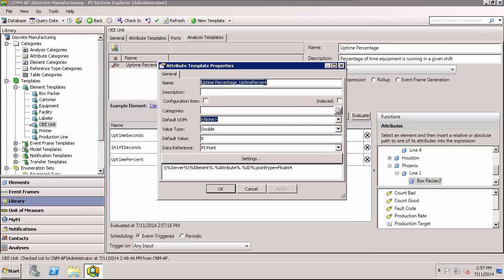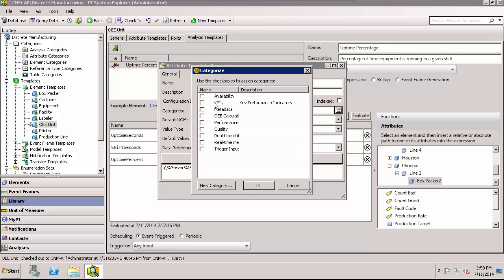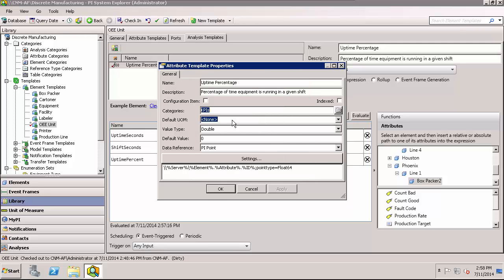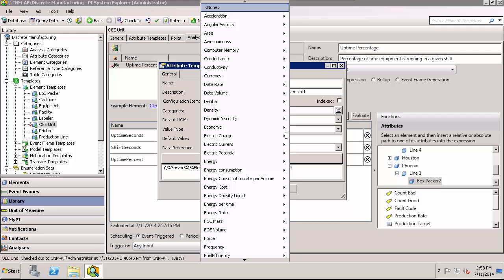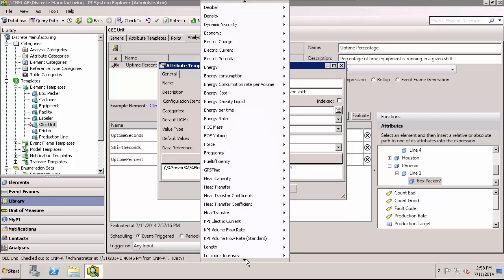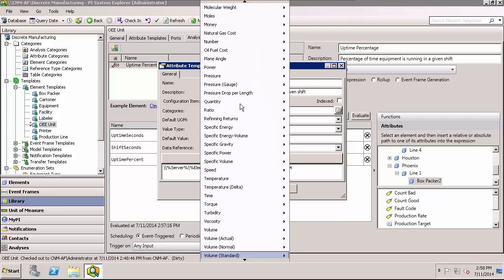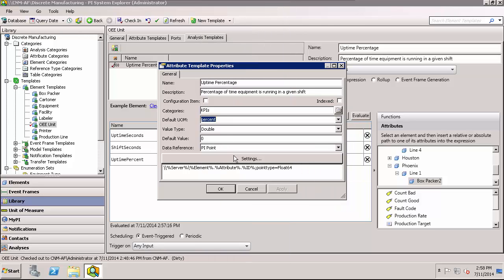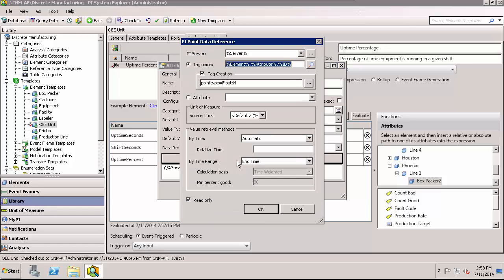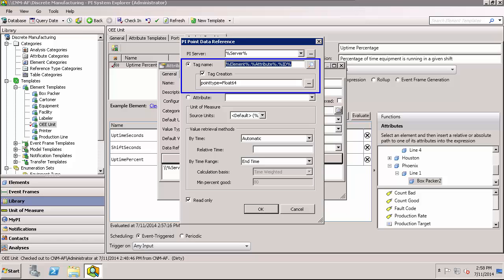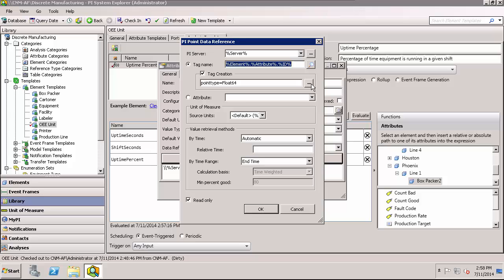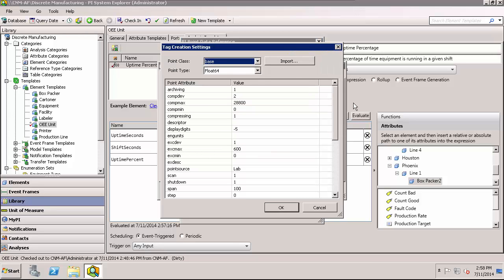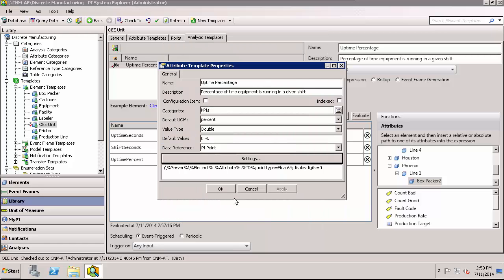And I'll give my attribute certain properties. To keep things nice and organized, I'll choose the KPI category. And it's always good to set a unit of measure to keep track of things. And I'm going to keep the data reference as PI point and select the settings. One of the exciting new options is the ability to write the analysis outputs to PI tags and to have those tags created through AF using this tag creation selection option. It's actually highly recommended to store the analysis to PI tags so that you can historize the data. And it also improves the AF performance. And I can even set the attributes of the PI tag here. So I'll hit OK.